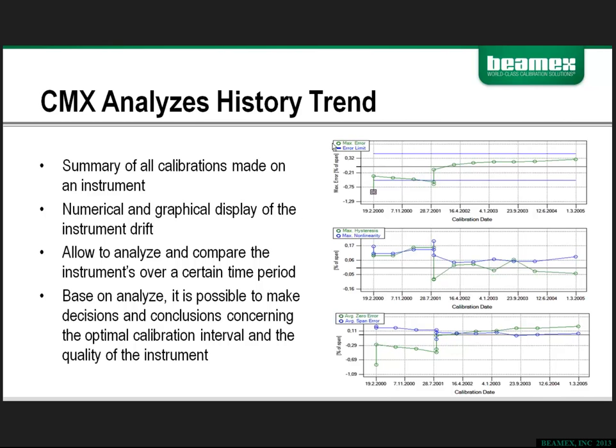Up in the top left, where that pointer is pointed right now, it gives you the understanding of what each color and line or circle represents. So the green circles represent the maximum error for that device, and the blue line represents the error limit, so in terms of highs and lows. So this blue line and this blue line would be the specified tolerance that the manufacturer provided for that particular instrument. And the green circle and the green line shows whether each calibration interval found it to be in tolerance or out of tolerance, and then the lines connect those to form the graph.